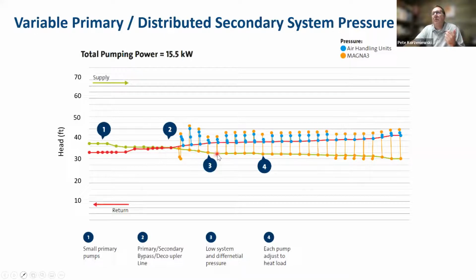The distributed pump is going to turn on as the load requires it to and pump through those friction losses that you saw in that terminal unit. It's going to take care of that itself. And then get through the air handler, have an exchange of heat, dump its chill water energy, pick up some heat and humidity, and then travel back to start the cycle all over again. So a few subtle differences, but a very different pressure profile when we're looking at putting those distributed pumps out into the system.